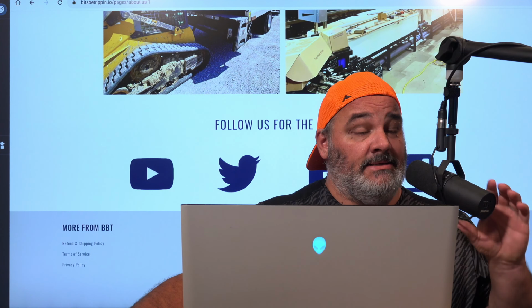And you guys have seen that if you watched the 2500 GPU video that we had a while back when we walked you guys through the GPU farm. There was a 3 megawatt service that we were only using about 1.5 megawatts of, but we had the switch gear in there. We showed you guys what that looks like and how the service comes in. That was 415, 240 service, stepped down to 208. So we had 208 service in there, and we had switchgear for that.